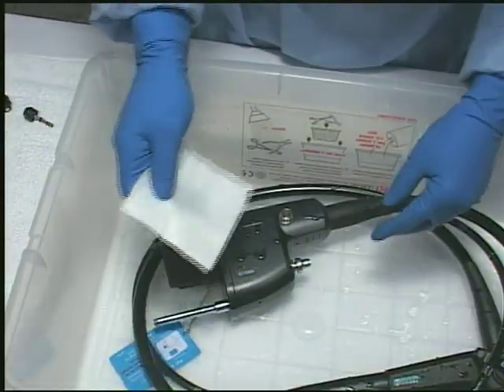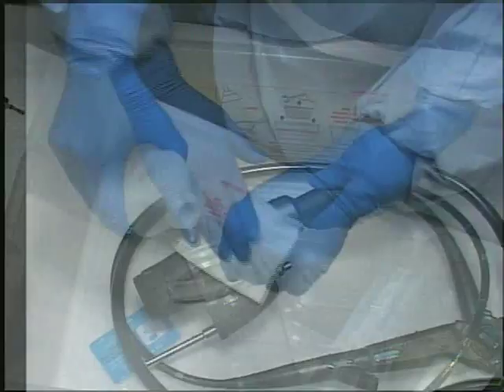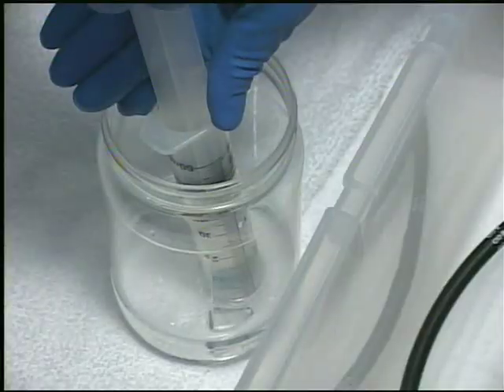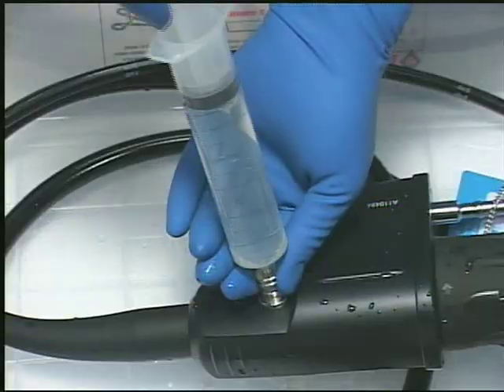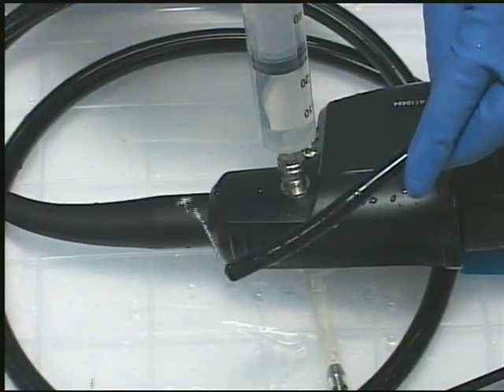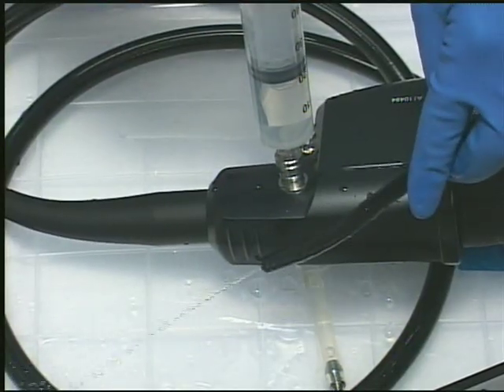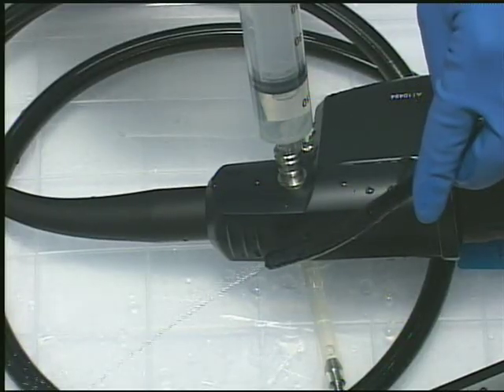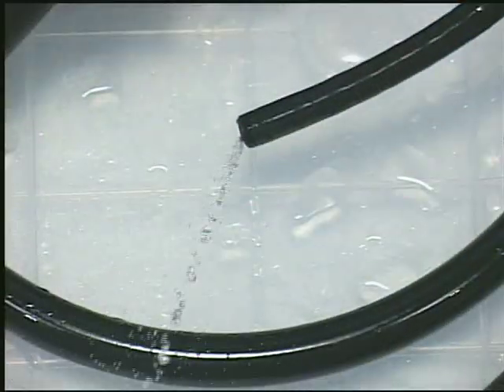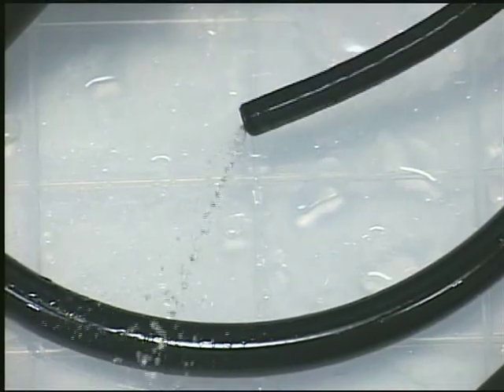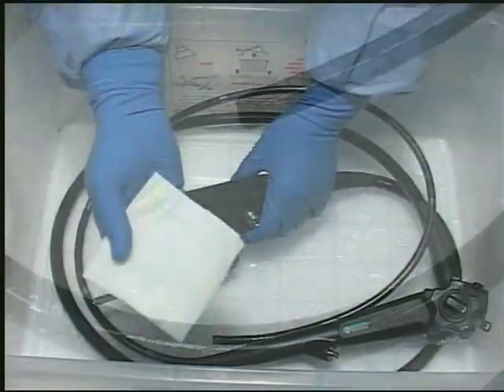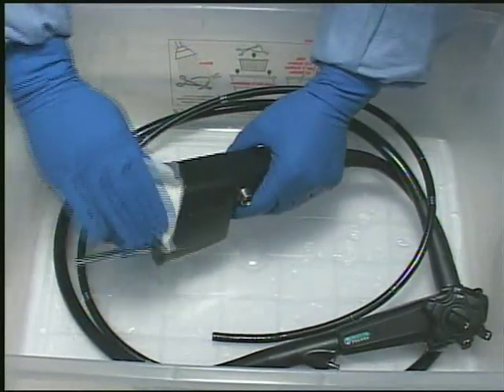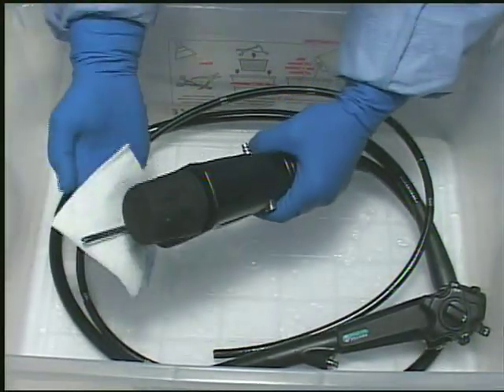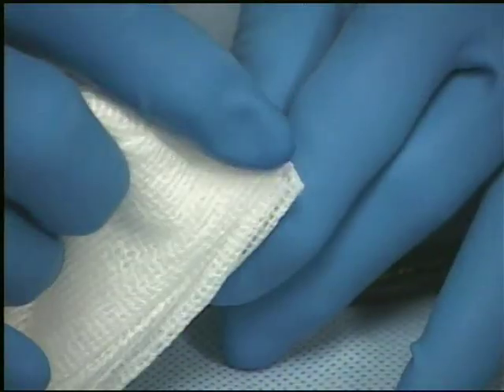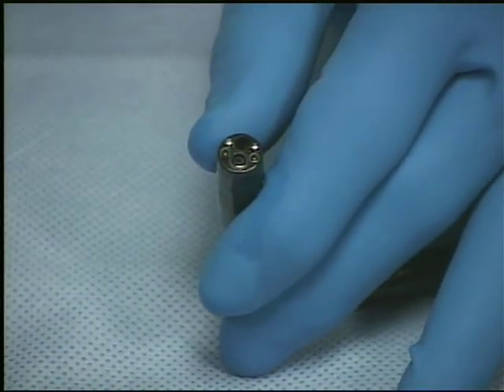Regardless of the quality of the rinse water used, a dry instrument achieved by a final alcohol rinse and forced air is essential to prevent bacteria colonization and/or infections associated with waterborne microorganisms. Such infections are more likely to occur when wet or contaminated instruments are used on patients whose immune systems are compromised or suppressed. Gently dry all external surfaces of the endoscope with a soft gauze or the like. Dry the objective lens with a lint-free cloth.